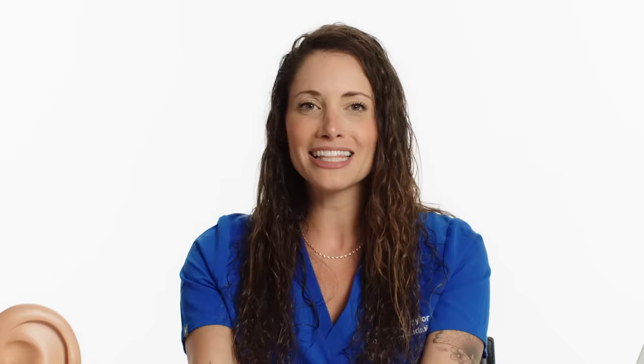That is why a hearing aid is so much more sophisticated — it's not just making things louder, it's trying to make things sound clear and natural. A hearing aid has a few different parts. This is an example of a hearing aid. Some of the main components are in this back piece, which sits behind your ear. In this tiny packaging, there is a very sophisticated chip. Some chips actually have what's called a deep neural network with 20 million sound samples stored on it, so that when you hear a sound, the hearing aid can put it on a map and figure out what it is — like a bird chirping or a tea kettle going off. There are also microphones on board, which send the signal to an amplifier, which is then produced through a speaker directly into your ear canal.